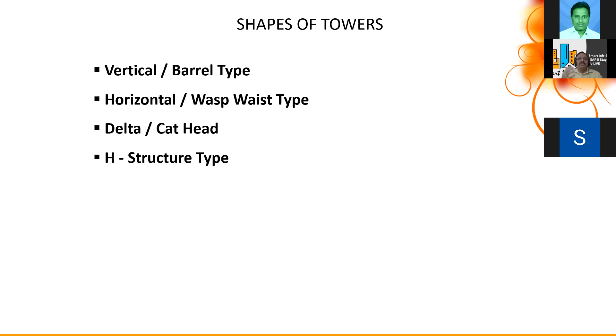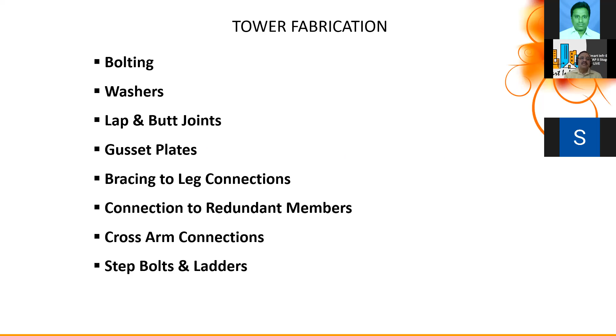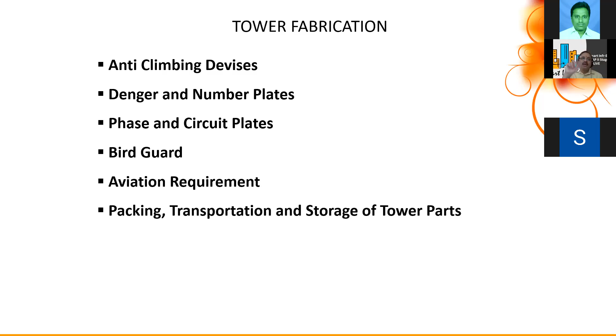Bolting and washers - normally towers are designed with bolted connections because they are easy to erect and maintain. There are lap and butt joints for splice connections; gusset plates are rarely used and minimized. Bracing to leg connections, connection to redundant members, cross-arm connections, step bolts, and anti-climbing devices are used. These are all safety features, along with danger and number plates, phase and circuit plates, bird guards for protecting birds resting on the conductor, aviation requirements, packing, transportation, and storage.